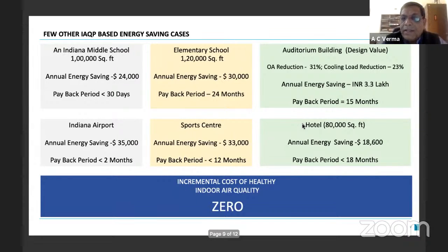It was applied in a hotel too. We applied it in an auditorium building at the design stage, and comparing the VRP procedure with the IAQP procedure, we found an outdoor air reduction of 31% was feasible, which reduced the cooling load by 23%. The energy saving alone is about 3 to 3.5 lakh rupees annually. Since the cooling load is reduced, the capital cost of the project also reduces, the AC plant size reduces, giving a payback period of 15 months.